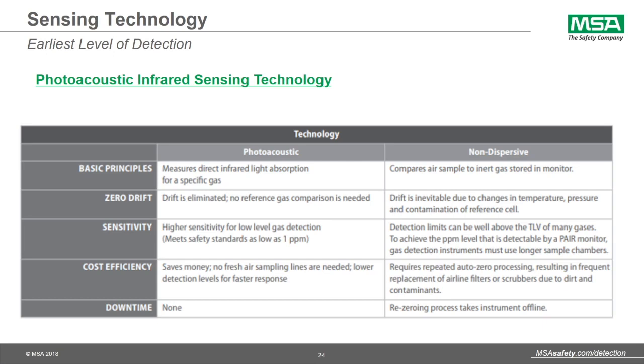And probably the most important aspect of the monitor is the sensing technology. MSA uses photoacoustic infrared sensing to detect a leak at 1 part per million. The technology uses a highly sensitive microphone that detects only the gas of interest as it is introduced to an infrared light source. I have a brief animation that shows exactly how the technology works.